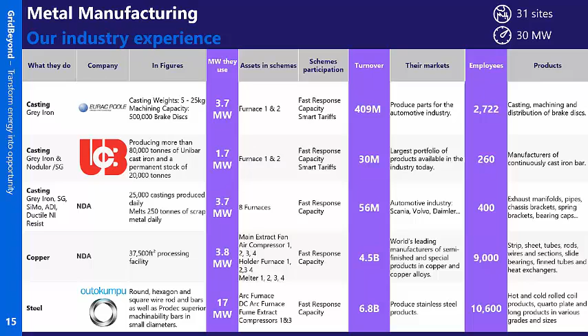So Eurac - what we have here is a hybrid solution. We've actually put a battery on the ground at this site. We audited its load, looked at their half-hourly data, and saw that this site was suitable for a 1.6 megawatt battery. With a partner, we've installed that battery, and it covers the site during peak tariffs.